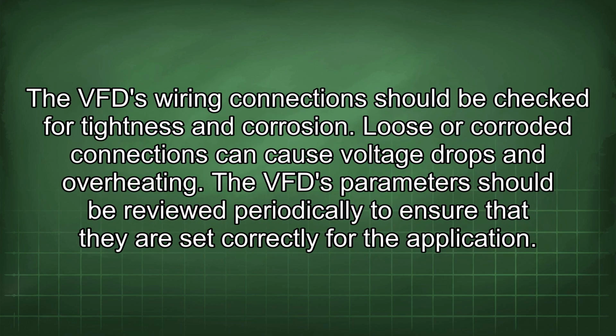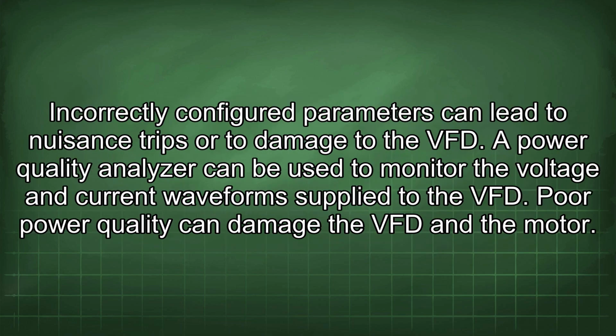The VFD wiring connections should be checked for tightness and corrosion. Loose or corroded connections can cause voltage drops and overheating. The VFD parameters should be reviewed periodically to ensure that they are set correctly for the application. Incorrectly configured parameters can lead to nuisance trips or to damage to the VFD. A power quality analyzer can be used to monitor the voltage and current waveforms supplied to the VFD. Poor power quality can damage the VFD and the motor.